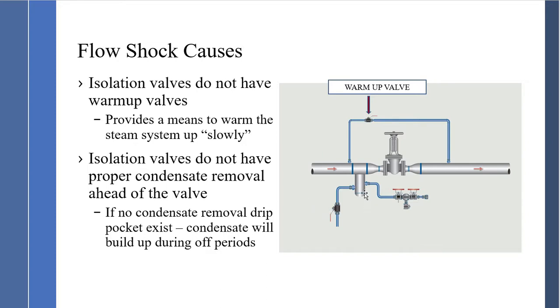Good practice also includes installing a drip pocket ahead of any valve that is shut — whether a control valve or isolation valve. This steam trap station removes condensate that can accumulate when a valve is closed for eight to ten hours. The last thing you want is to open the valve and allow a slug of condensate to flow into the steam line. Two key measures for flow shock prevention: always have a warm-up valve around the isolation valve, and include a steam trap station ahead of it.